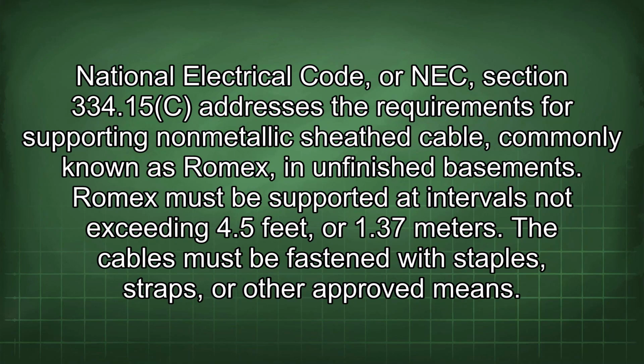National Electrical Code, or NEC, Section 334.15c addresses the requirements for supporting non-metallic sheath cable, commonly known as Romex, in unfinished basements. Romex must be supported at intervals not exceeding 4.5 feet, or 1.37 meters. The cables must be fastened with staples, straps, or other approved means.